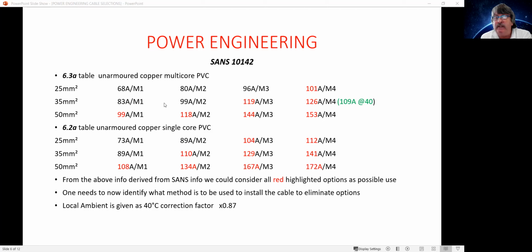I've gone for a basic type of arrangement. So we said that we could have a look at some single core cables, first 25 meters, not particularly long. And we could go for unarmored copper multi-core PVC. And we've chosen PVC so we don't clutter up this. If we had aluminium, for instance, there would be maybe a little bit extra worry and concern about the current carrying capacity of aluminium in much the same way that it would form in this one.